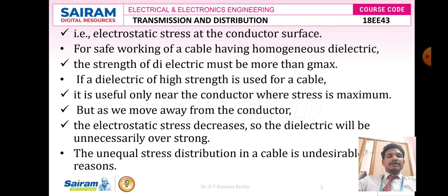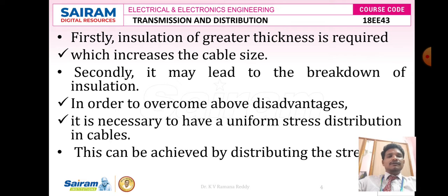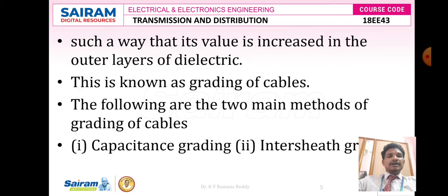In order to make the electrostatic stress uniform and overcome voids in the hard insulating material, note that as we move away from the conductor the electrostatic stress decreases, so the dielectric becomes unnecessarily over-strong. Unequal stress distribution is undesirable: firstly, insulation of greater thickness is required, which increases the cable size; secondly, it may lead to breakdown of insulation. Therefore, it is necessary to have uniform stress distribution, achieved by increasing stress in the outer layers. This is known as grading of cables.